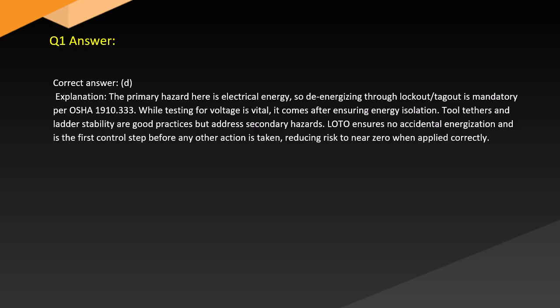Answer. Correct answer, D. Explanation. The primary hazard here is electrical energy, so de-energizing through lockout/tagout is mandatory per OSHA 1910.333. While testing for voltage is vital, it comes after ensuring energy isolation. Tool tethers and ladder stability are good practices but address secondary hazards. LOTO ensures no accidental energization and is the first control step before any other action, reducing risk to near zero when applied correctly.